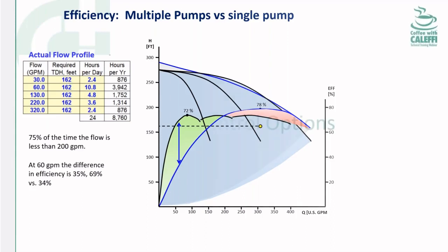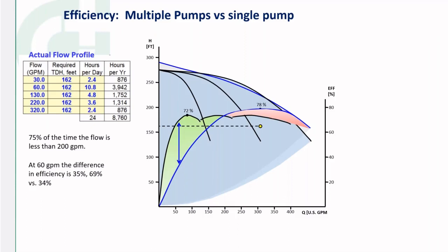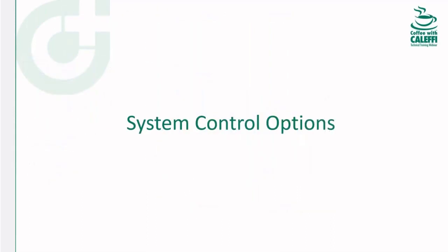So let's see. And that wasn't 25%. That was an efficiency difference of 35 percentage points. So at 60 gallons a minute, you're running at a pump efficiency of 69% or 34%. Yeah, I'll take 69 all day, all week, twice on Tuesday. That's right. All right. So no matter how well you select the pumps, it doesn't mean anything without proper sequencing.